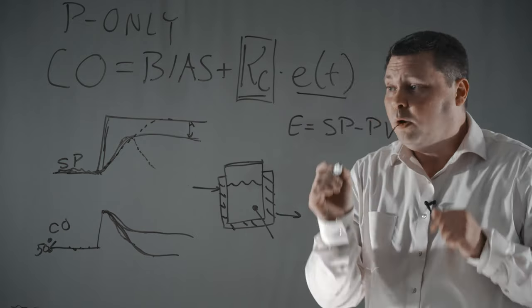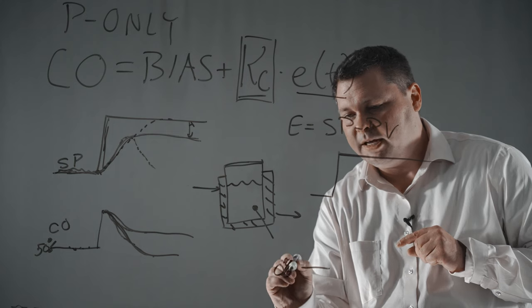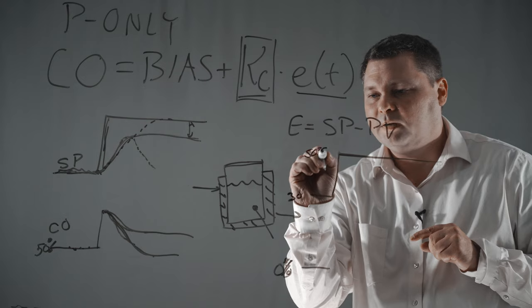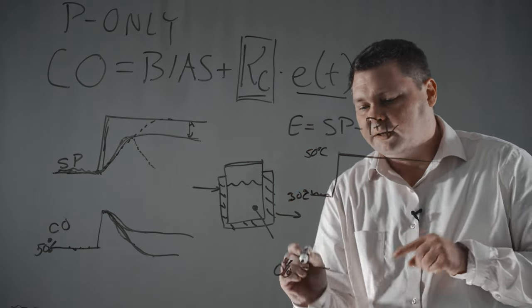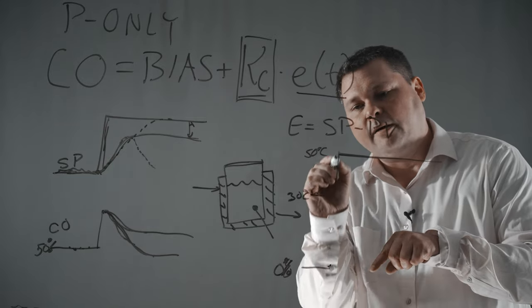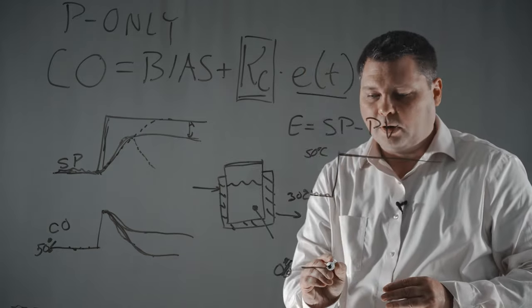Now let's say we want that temperature to go from temperature A to temperature B, and we're going to start at controller output of 0%. So we start at, say, 30 degrees and we want to go to 50 degrees C. Well, at the beginning here, we have no error. And all of a sudden, we now have an error when we change the set point. Same thing has happened over here. Our controller output is going to jump, which means we're going to add steam into the system. We introduce heat, and the heat starts to make the temperature rise.